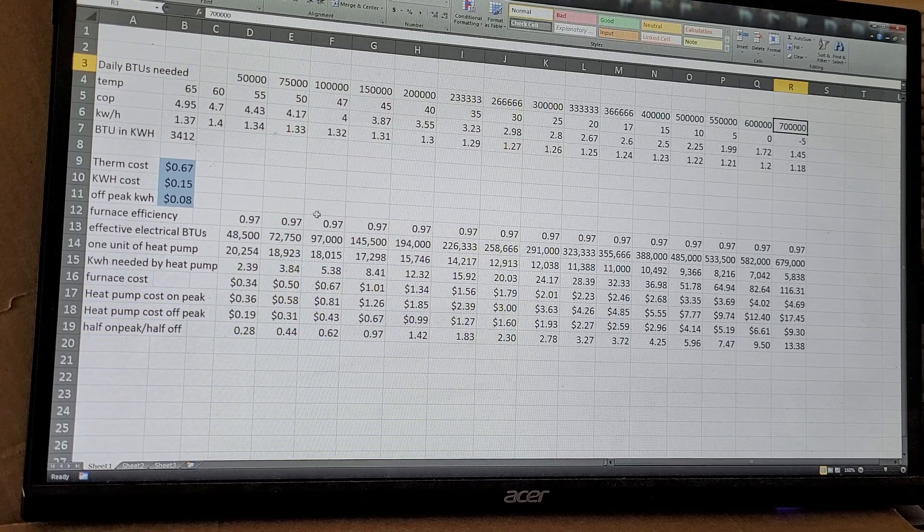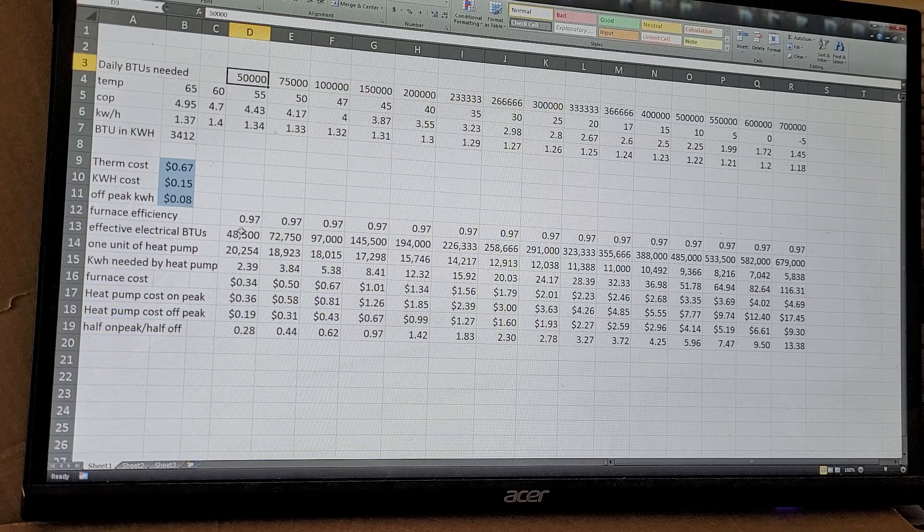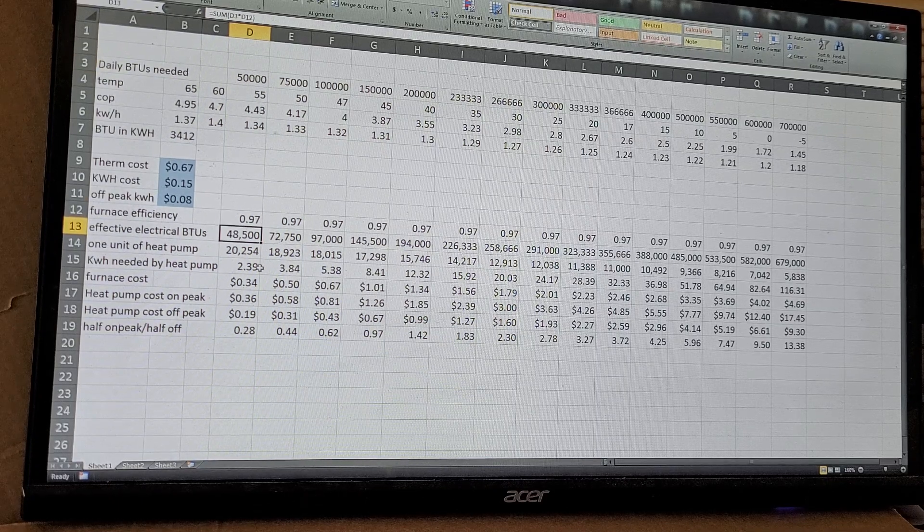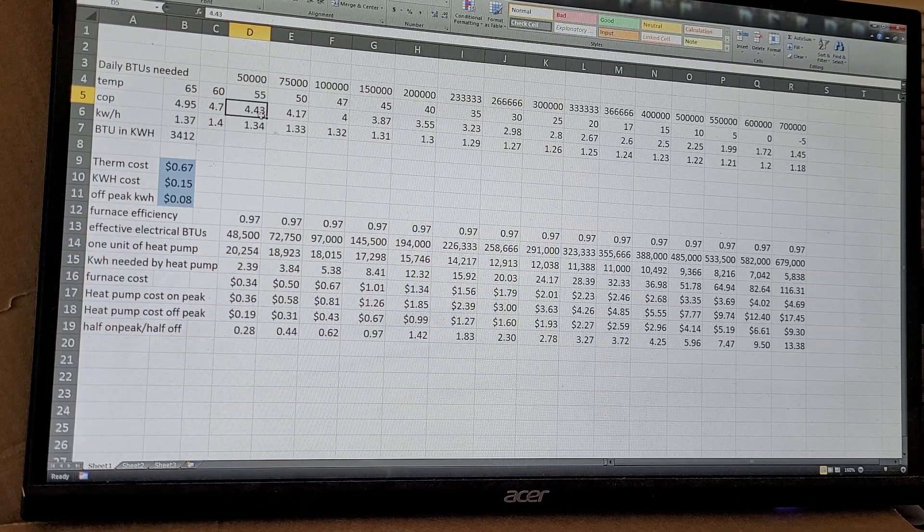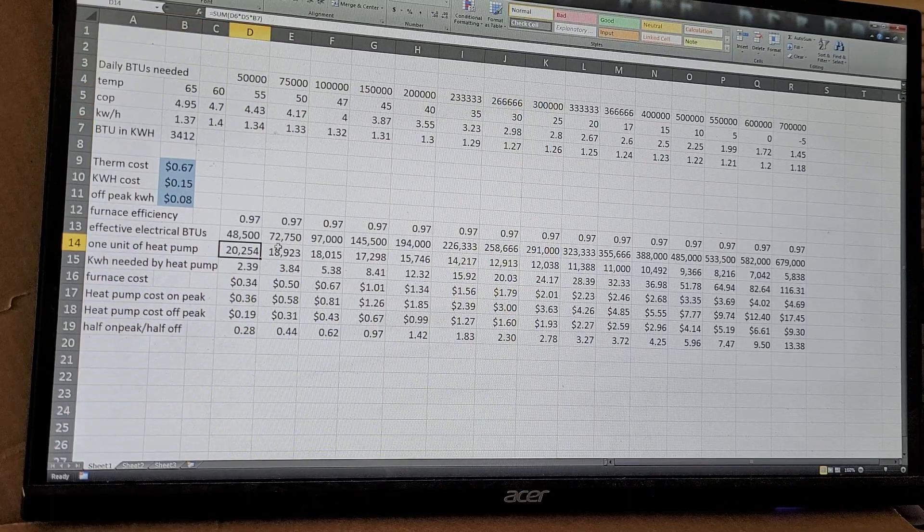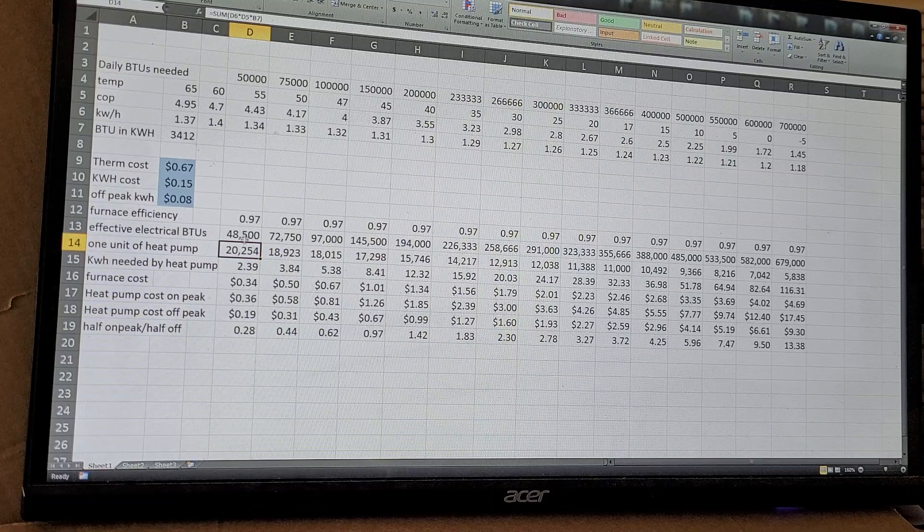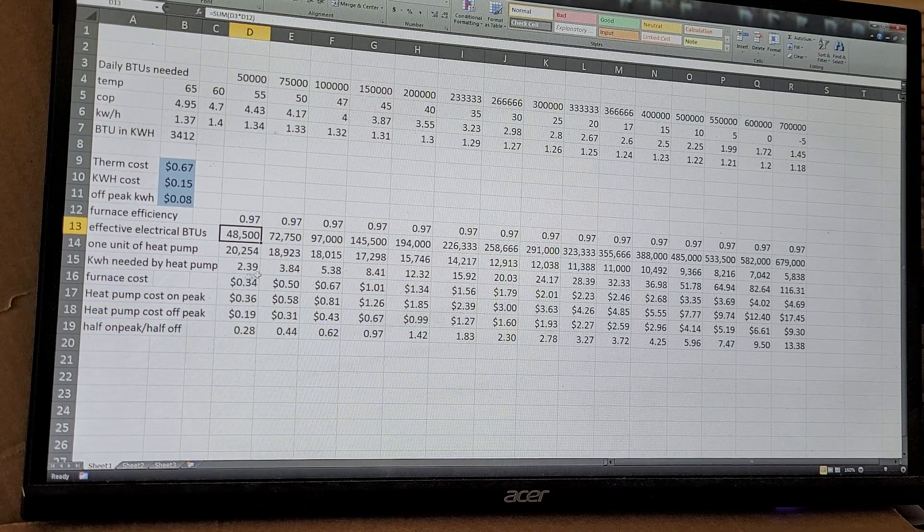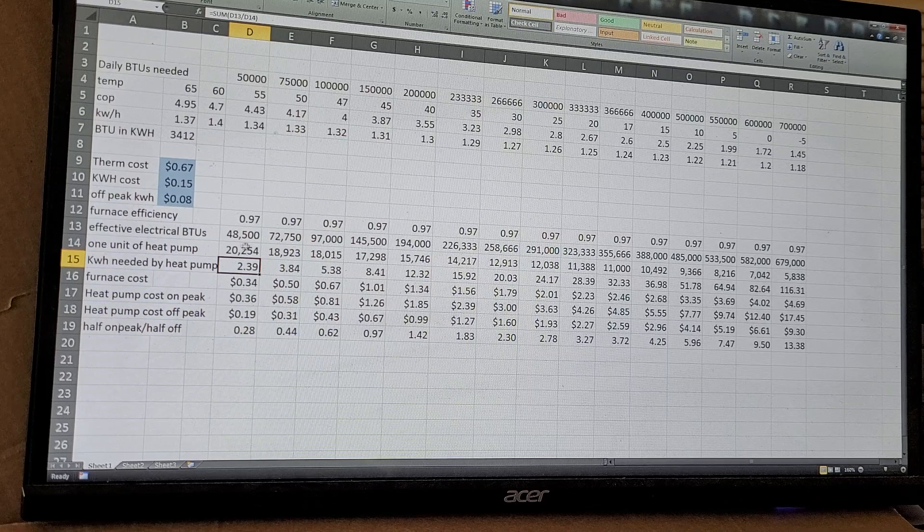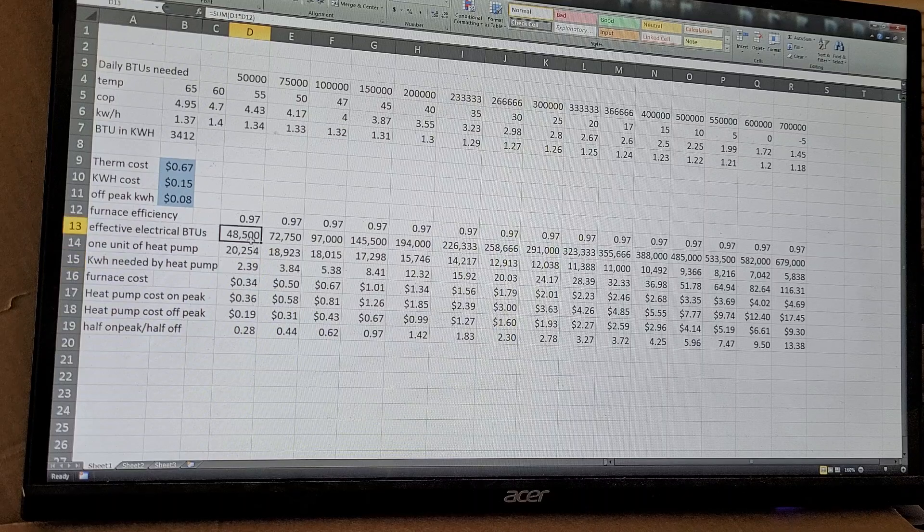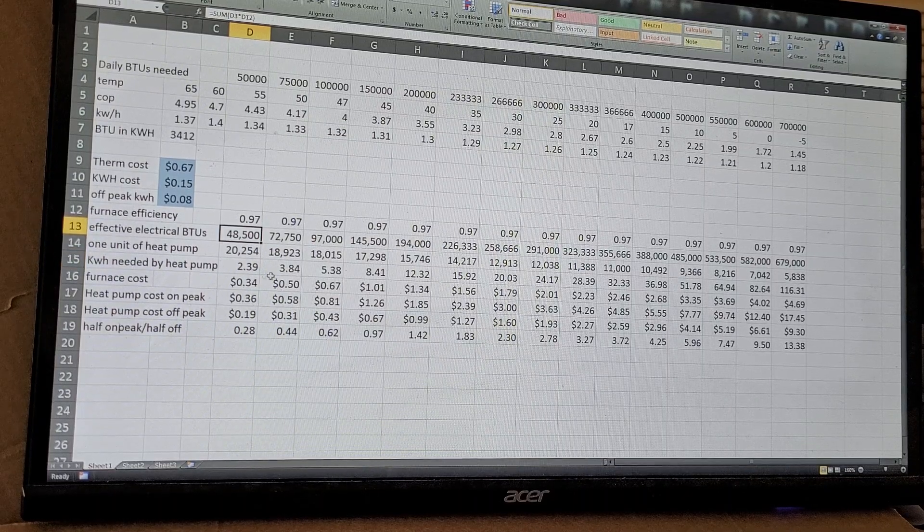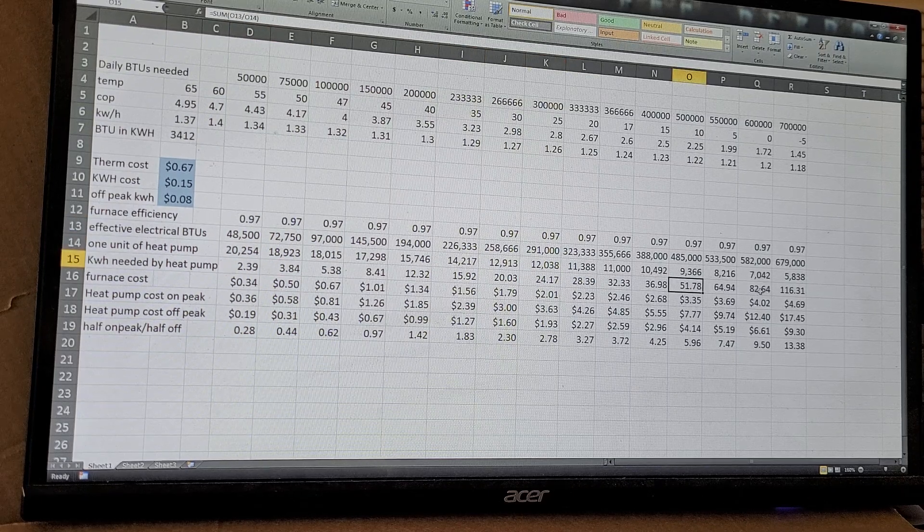Now what it means by the effective electrical BTUs is I just took this, multiply by 0.97, so this is how many BTUs I would need to be equivalent to the furnace. So one unit of the heat pump at a 4.43 times of what you can get for one BTU gives you this many. So you'll need to use a little over, not even two and a half times, to get the same amount of BTUs out of a kilowatt hour. So you're going to need to use this many kilowatt hours to get the same as one therm, the same amount of energy used in the heat pump. So as it gets colder, the kilowatt hours increase, and they increase by a lot.